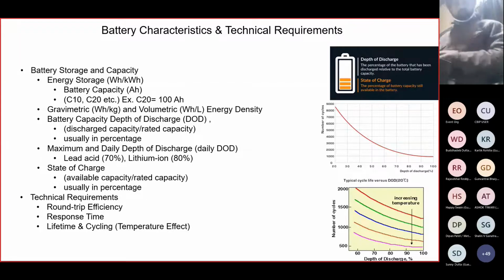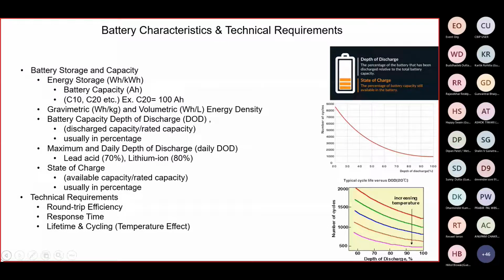The other characteristics or specifications are the depth of discharge and the state of charge. The depth of discharge is the amount of the battery's total capacity which has been consumed, and both the depth of discharge and the state of charge are given in percentage. The maximum and the daily depth of discharge is usually set. For lead acid it is recommended at 70%, and for lithium ion it is recommended at 80%. That is because this depth of discharge is directly dependent on the number of cycles, which you can see on the right side of the slide. And this is easily available in the manufacturer sheets.